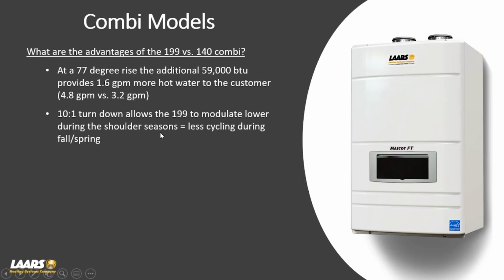Also, on a 199, you get a 10-to-1 turn down. What that means is we can modulate lower on a 199 versus a 140. The 140 is only a 5-to-1 turn down. So example, we can modulate on a 199 all the way down to 19,900 BTUs. A 5-to-1 turn down on a 140 modulates down to 28,000 BTUs, which is still a great turn down. However, during your shoulder months, you may not need a lot of heat, and you've got a larger modulation on the 199, so we get a larger turn down.